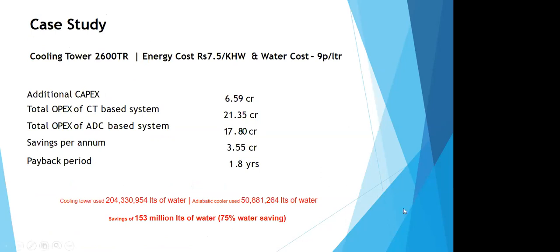Now we look at a case study whereby we had supplied adiabatic coolers in a region which was scarce of water. The capacity of the adiabatic cooler was around 2600 TR. The energy cost was around 7.5 rupees per kilowatt hour, and the water cost was 9 paisa per liter. The additional capex for the adiabatic cooler was around 6.6 crore. The operating cost of the conventional cooling tower based system was around 21.35 crores. These are all annual figures. And the operational cost for the adiabatic cooler system came to around 17.8 crores. There was a net saving of around 3.55 crores by using the adiabatic cooler.